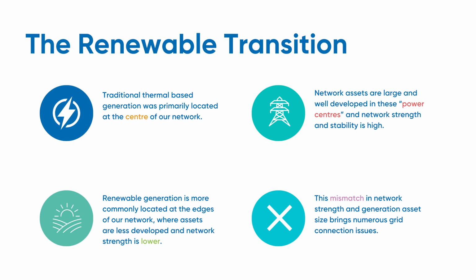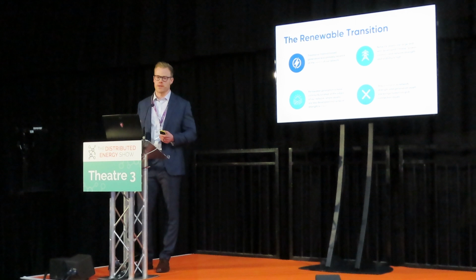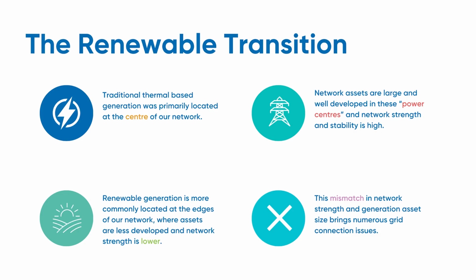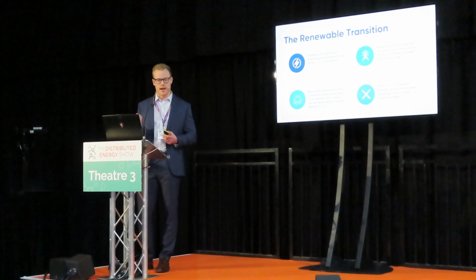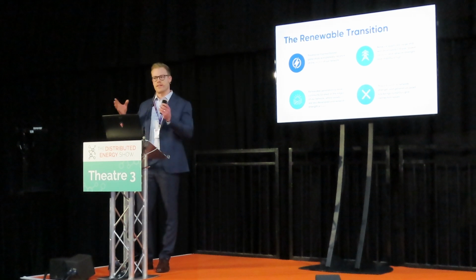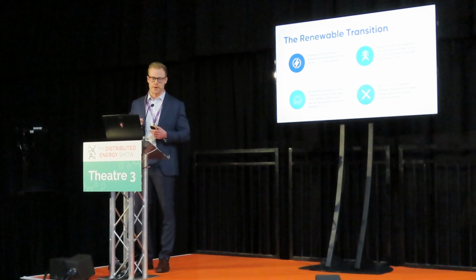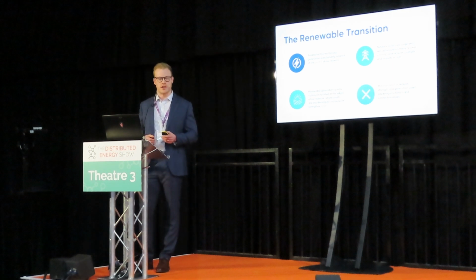This has now been completely flipped on its head, because if you think about it, where all of the natural resources are for wind, solar, they're not located centrally to the UK. They're more likely on the edges. So we're now trying to connect multi-megawatt, gigawatt wind farms and solar farms at these very weak areas of network. And we're trying to then transmit that power all back into the center where the network's just not made to do that. So these are the kind of issues we're coming across. There's a mismatch in the network strength and stability and the size of the asset that we're actually trying to connect to that network, which causes these types of grid connection issues.